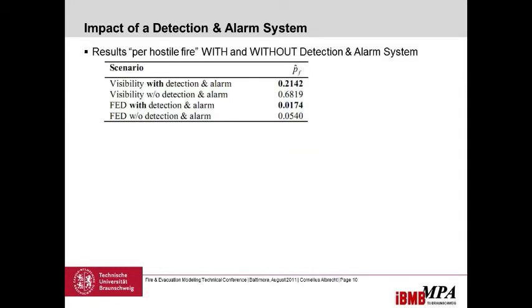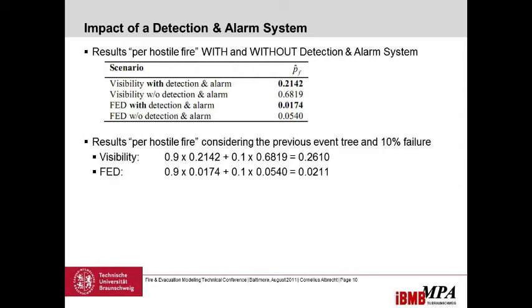The results — per-hostile-fire, with and without the detection system — show that when the detection system is added and functional, the probability goes down from about 70% to 21% for visibility failure, and for incapacitation it goes down from 5% to about 2%. Accounting for the 10% system failure probability: in 90% of cases we use the lower failure probability, and in 10% we use the 70%. In total, we get about 26% failure for visibility and about 2% for FED, already including the 10% alarm system failure.